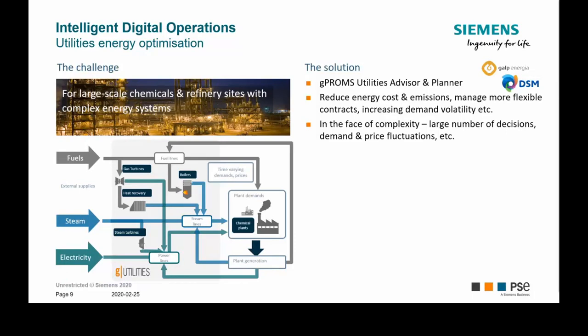Before presenting the solution, let me mention some typical challenges for online optimization. One challenge is knowing how much electricity is being generated on-site — by boilers, gas turbines, and so on — and how much needs to be bought from the energy supplier. Of course you need to know the electricity price, which changes by the hour, to have a good prediction of your economics. Another challenge is steam distribution efficiency and how to deal with steam venting and reduce it.